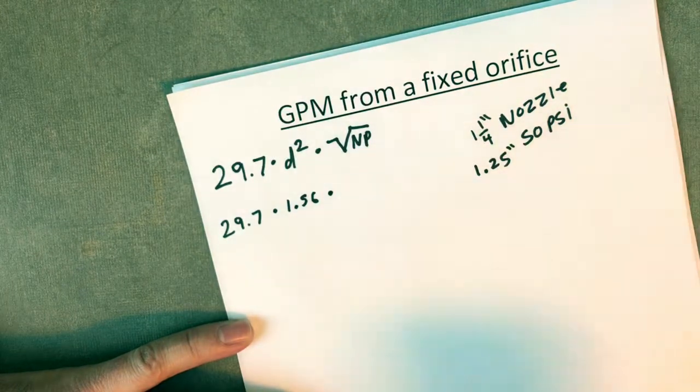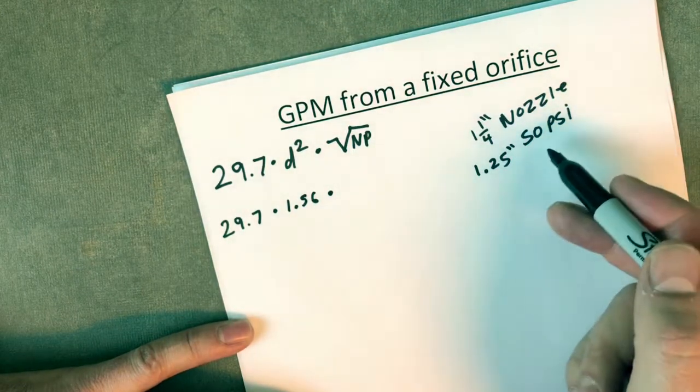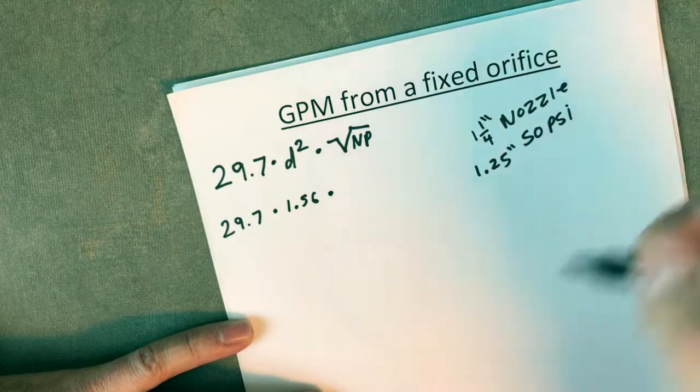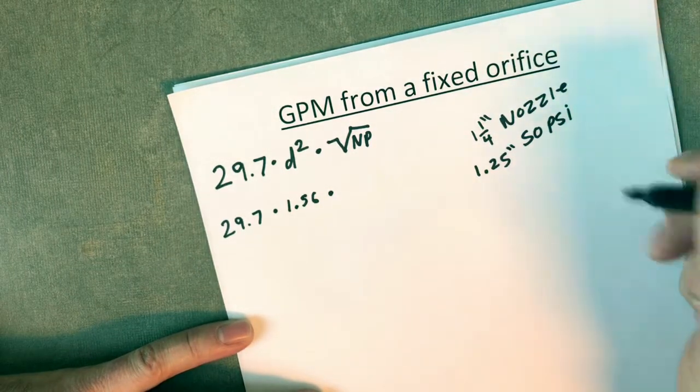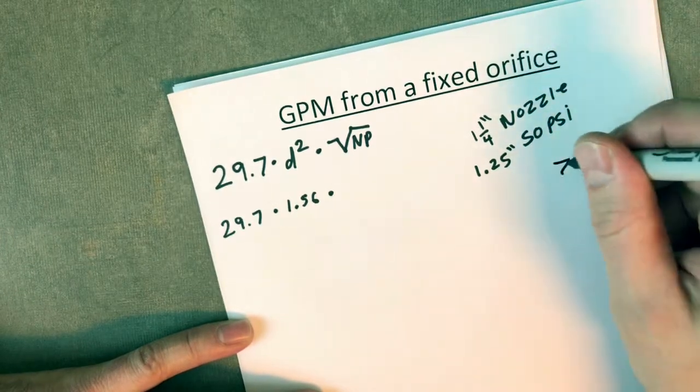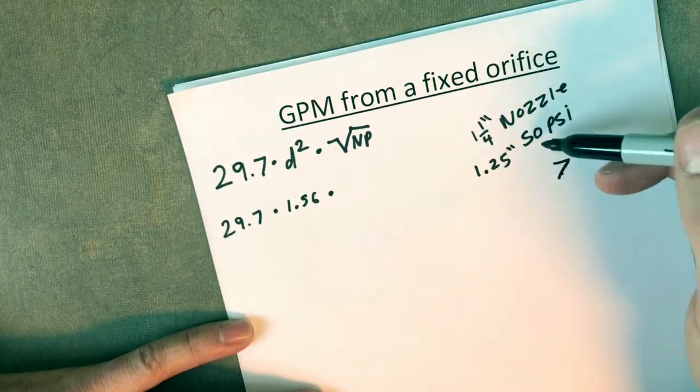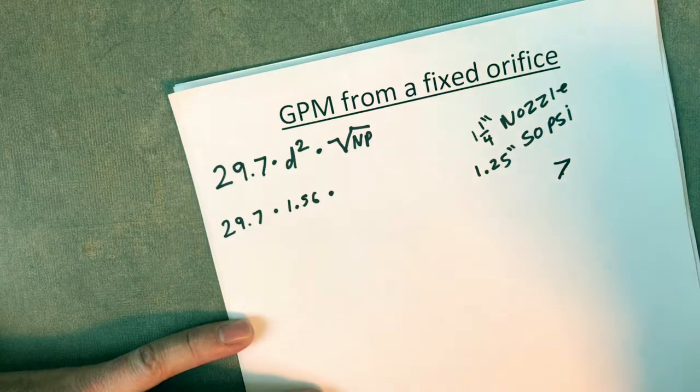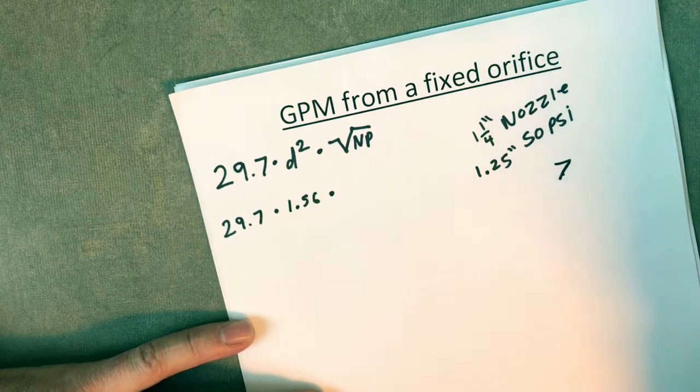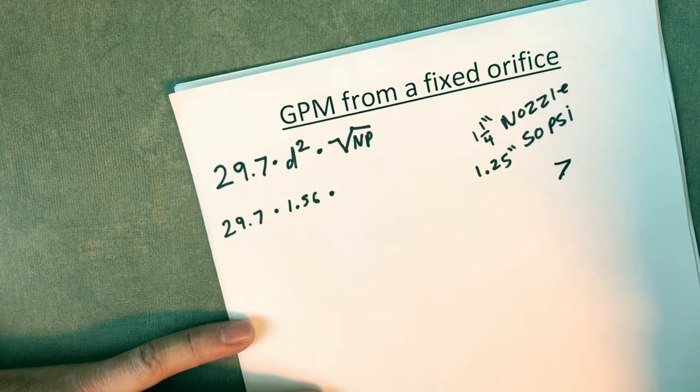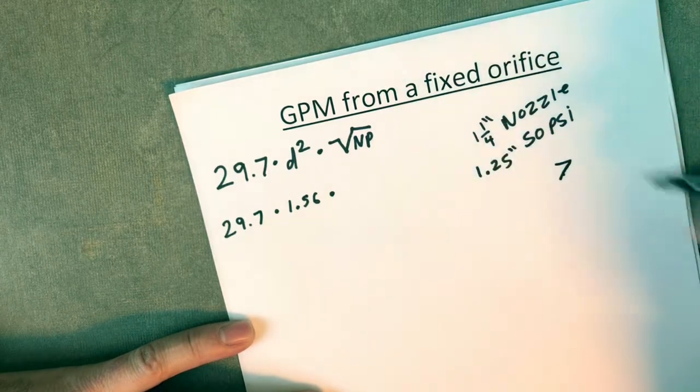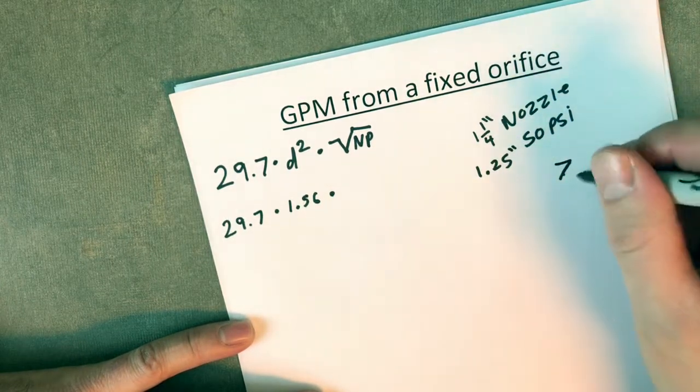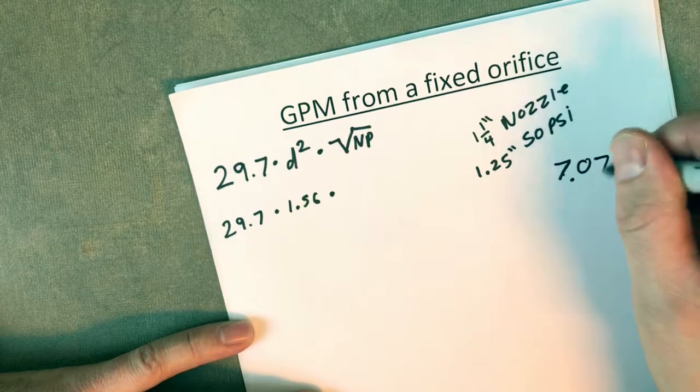Times the square root of the nozzle pressure, 50 psi. If you're doing an engineer's exam, be super accurate with your numbers. If you're just doing field calculations, you could use 7. 7 times 7 is 49, gets you close enough. But if you're taking a test, actually use the correct numbers. Carry it out a couple decimal places. The square root of 50 is 7.07.